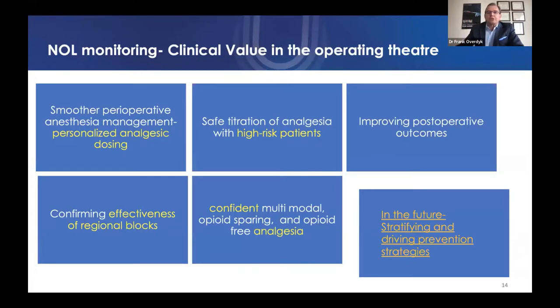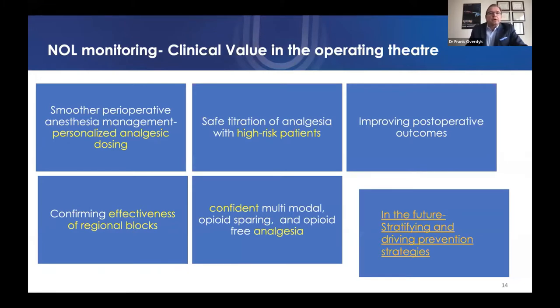The value proposition for NOL is quite extensive. The monitor allows personalized analgesic dosing, responding to actual sympathetic output from the patient to noxious stimuli, rather than relying on typical doses and experience. This is especially useful in patients at risk for overdosing or underdosing, such as opioid-tolerant patients or the very frail or elderly. NOL is also ideal for assessing whether a regional nerve block is working and confirming adequate analgesia during multimodal techniques, ERAS protocols, or even opioid-free anesthesia.